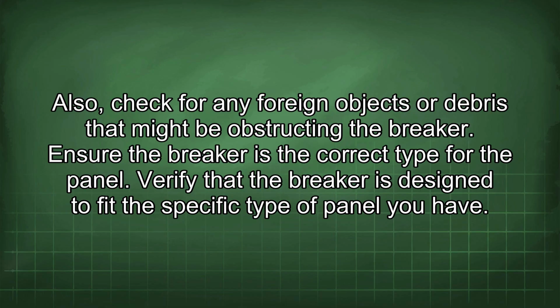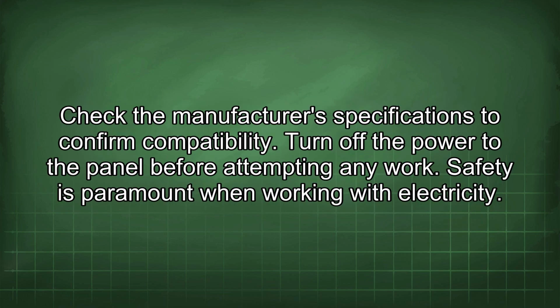Ensure the breaker is the correct type for the panel. Verify that the breaker is designed to fit the specific type of panel you have. Check the manufacturer's specifications to confirm compatibility. Turn off the power to the panel before attempting any work.